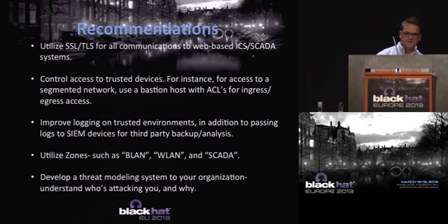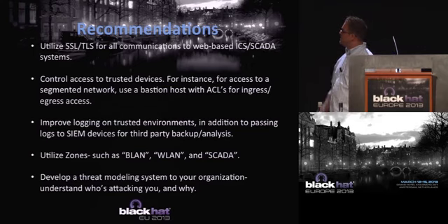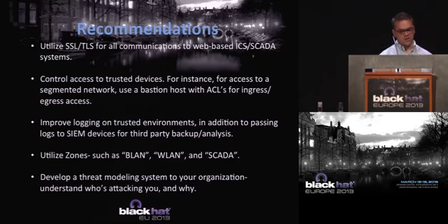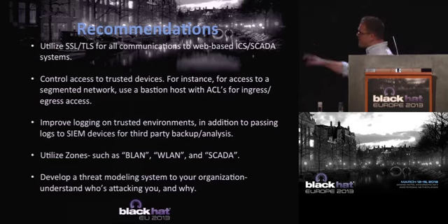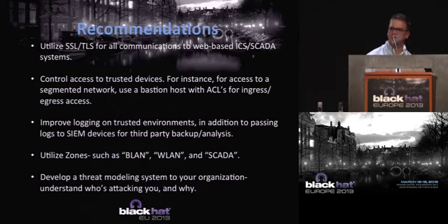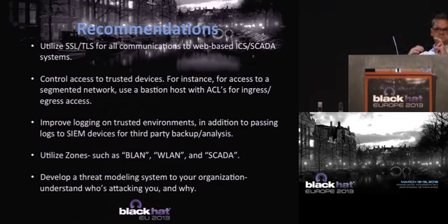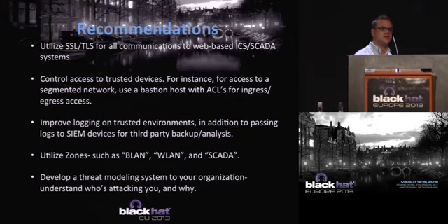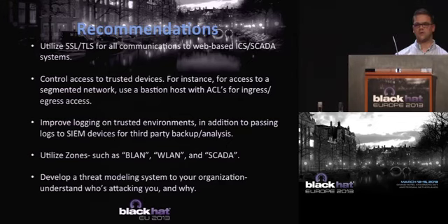Utilize SSL, TLS for communications. That's common, I think, for pretty much anything. Control access to trusted devices. Again, that kind of goes back to the same concept of controlling access from a contractor standpoint. So use a Bastion host with ACLs, and whenever I say a Bastion host, I'm referring to a central server that is actually in between two different WAN segments. So between a SCADA WAN segment and a PLC segment, put a Bastion host, and that's the only host that can gain access into that network.